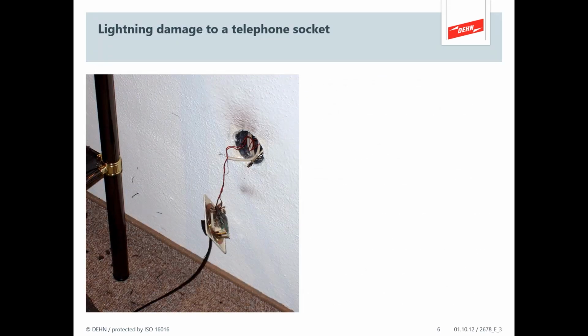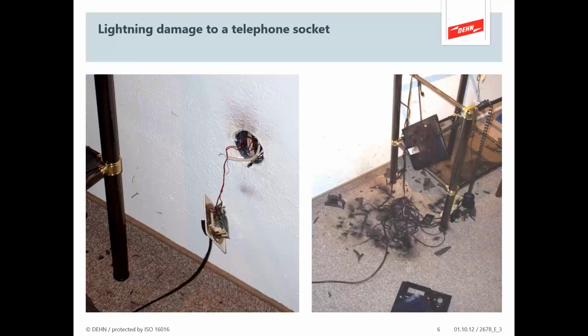So here's an example. We've got a domestic dwelling, and let's imagine we've got an SPD in the consumer unit. Now I know from my personal experience at a place I used to live in that I did have an SPD in the consumer unit. But then there was a nearby lightning strike on a house about 200 meters from where I live. And this looks pretty much like my master socket looked like. So yes, it was a bit charred and it completely blew up, and you can see that situation here. And also we had a situation where the telephone itself was blown to bits. Same for me, and also the microfilter and the router were taken out as well.